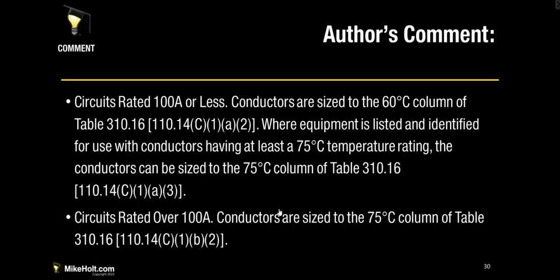So we'll jump into a couple of comments here. For circuits rated 100 amps or less, conductors are sized to the 60 degrees Celsius column of table 310.16, where equipment is listed and identified for use with conductors having at least a 75 degrees Celsius temperature rating. The conductors can be sized at the 75 degrees Celsius column of table 310.16. For circuits rated over 100 amps, conductors are sized to the 75 degrees Celsius column of table 310.16. That's an important slide right there.